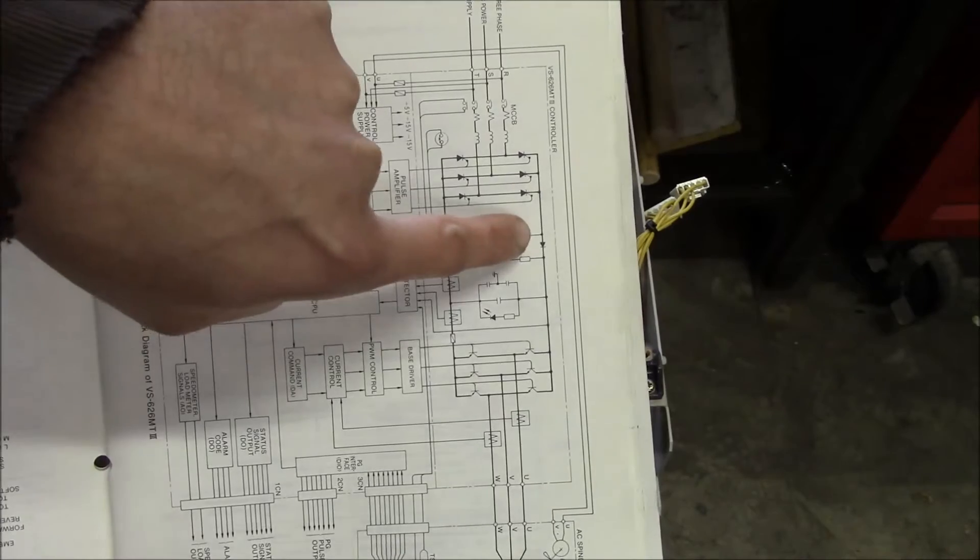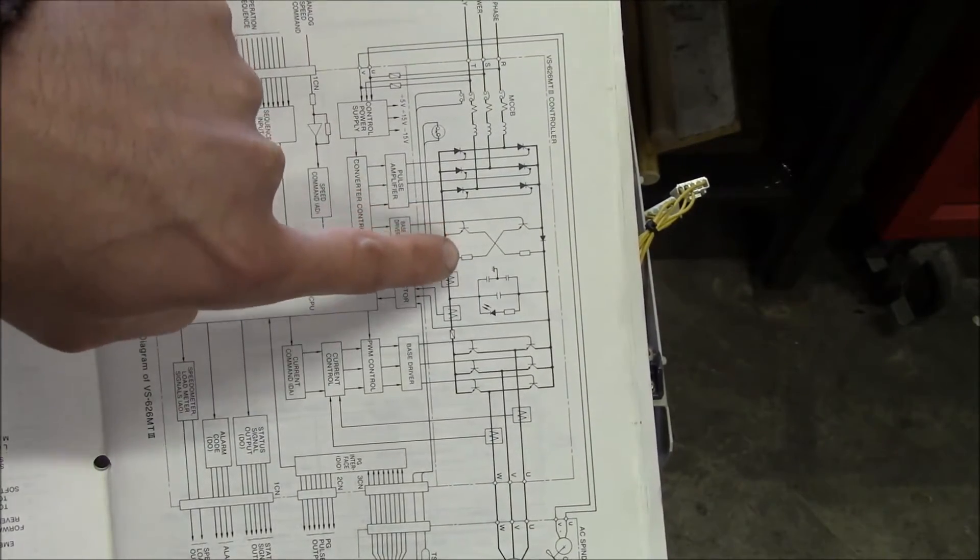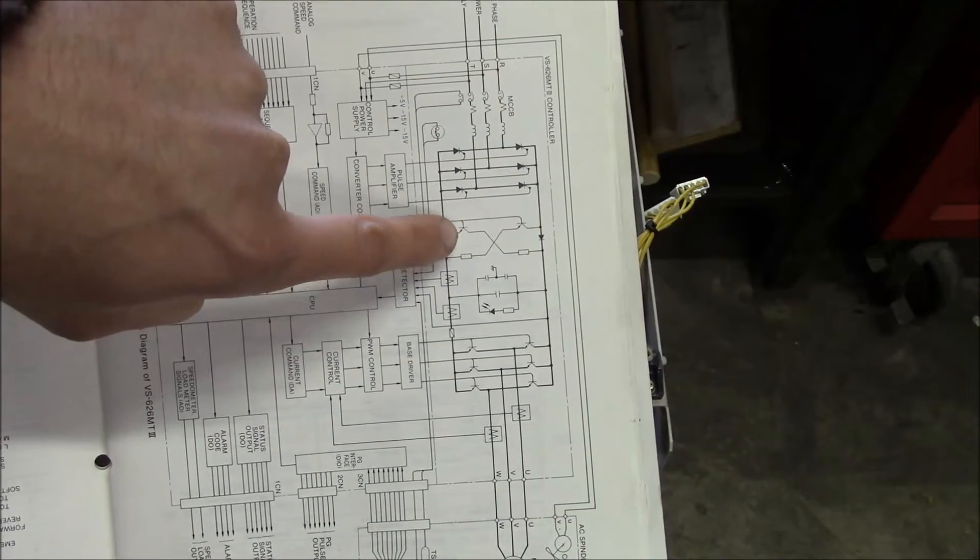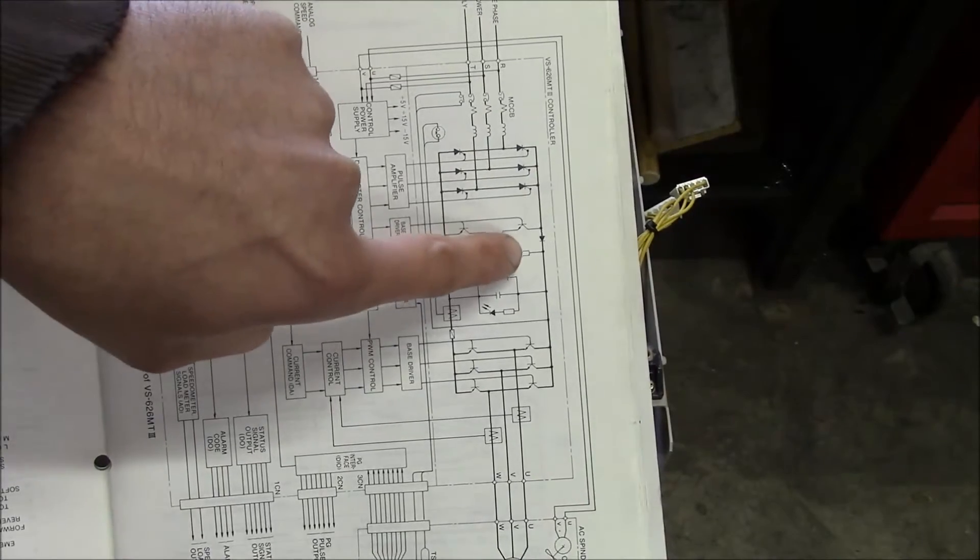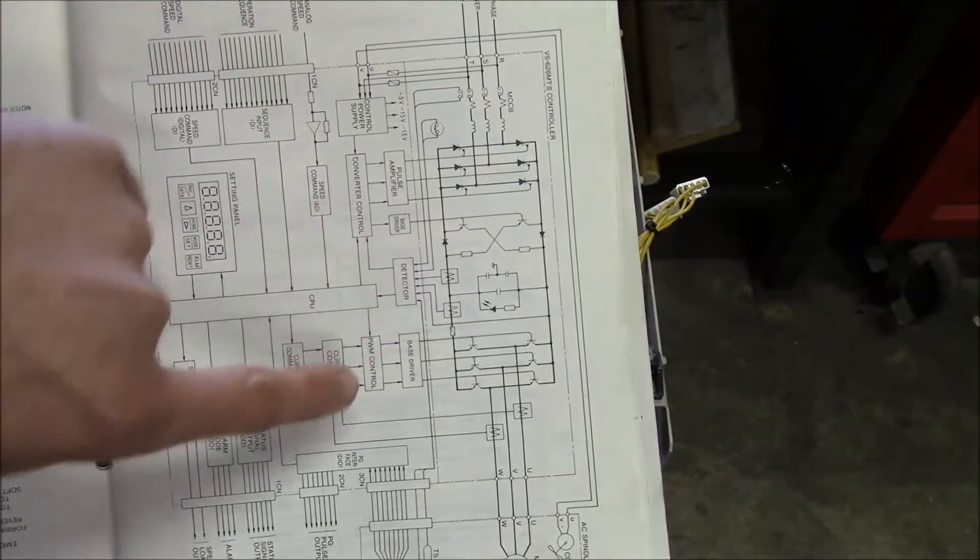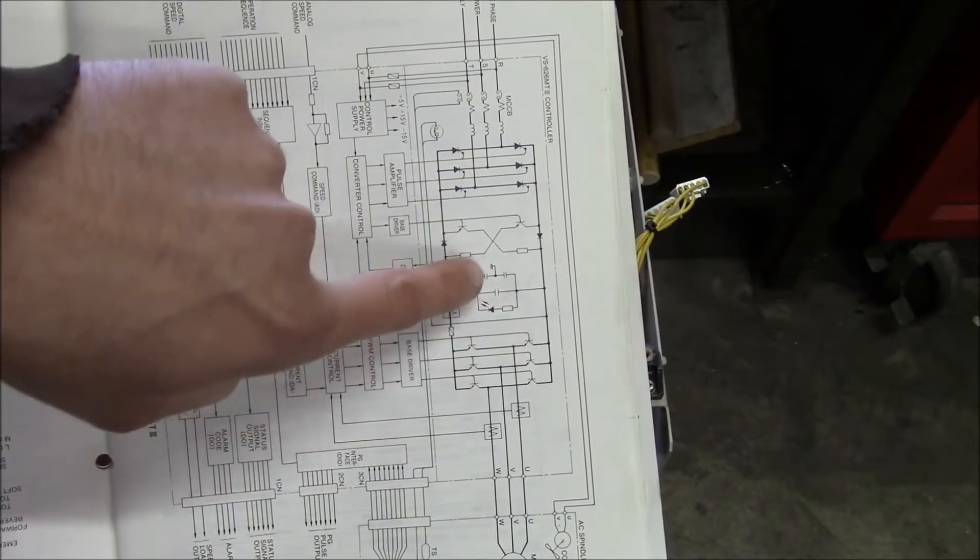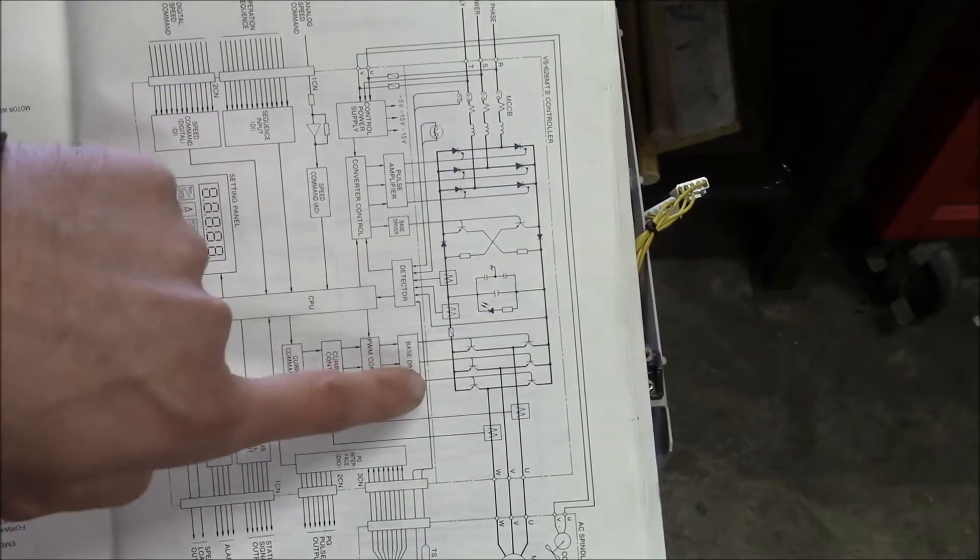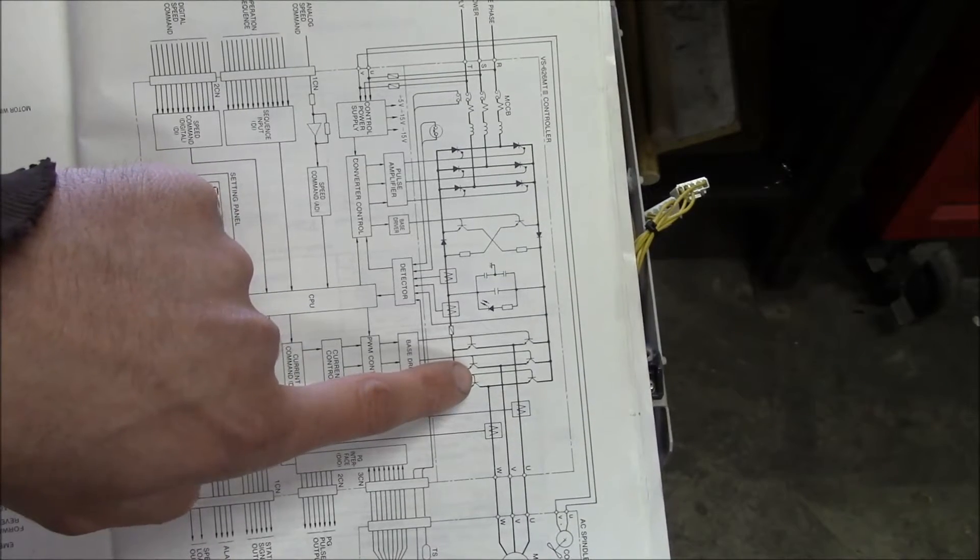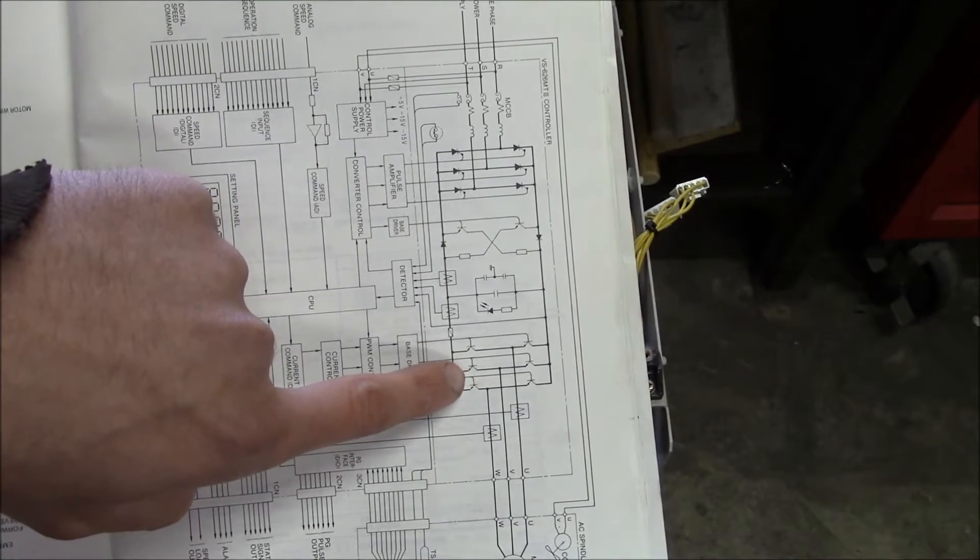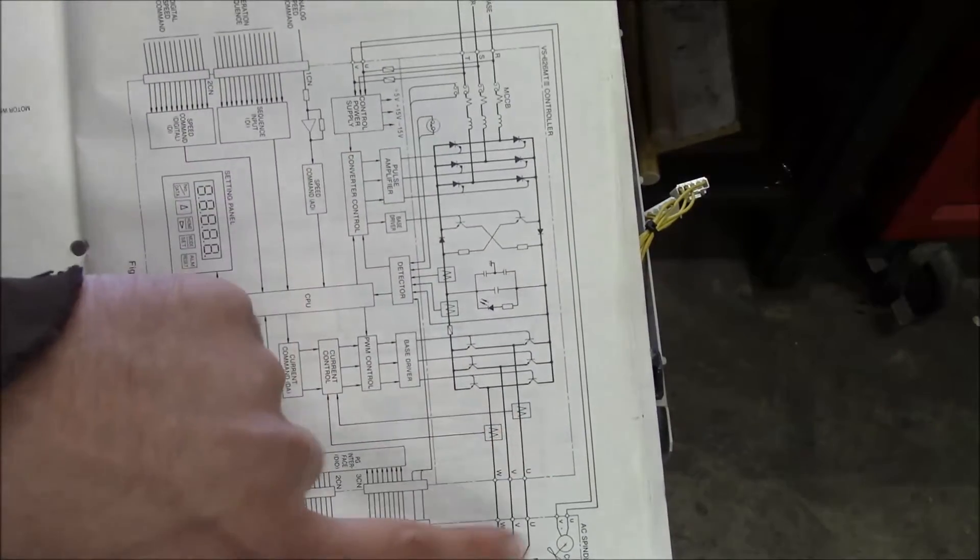And then there's two IGBT transistors that basically fire to do the braking. So these are the braking resistors here, shown by these little boxes. And then this right here is a big capacitor. And then there's some other circuitry involved with that. And then it comes down here to a set of transistors that take the DC bus and turn it back into three-phase power to run the motor.